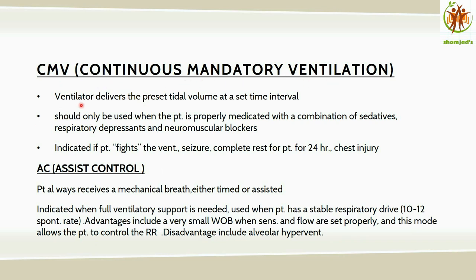CMV — continuous mandatory ventilation: the ventilator delivers a preset tidal volume at set time intervals. It should only be used when the patient is properly medicated with sedatives, paralytics, and neuromuscular blockers. This mode is typically used when a patient needs to be fully ventilated for at least 24 hours — for example, patients who are fighting the ventilator, seizure patients, or chest injury patients. The machine does not respond to the patient's respiratory drive and delivers continuous ventilation at the preset tidal volume and timing.